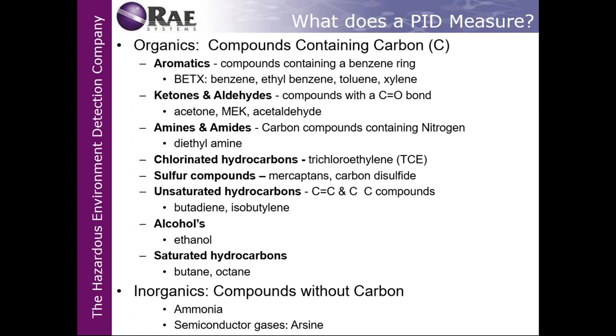So if you use a 4-gas with a PID monitor, I would check with your manufacturer. In particular, for RAE Systems, the correction factor for ammonia is 32.2. I'm not familiar with other manufacturers, but I certainly would consult with their technicians and find out, because I notice a lot in food manufacturing, as well as firefighting, when you're dealing with cooling agents like ice rinks, ammonia is very, very important. A lot of ammonia sensors will top out at anywhere from 100 to 300 parts per million. If you want to get higher than that, you have to go to a PID.